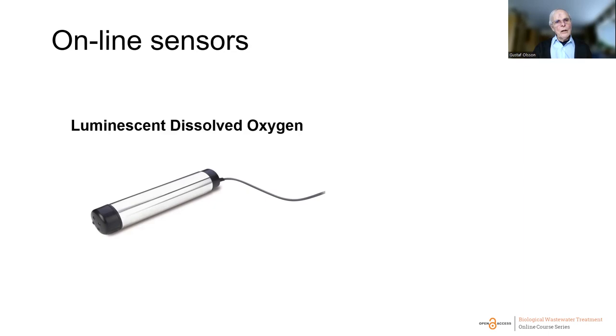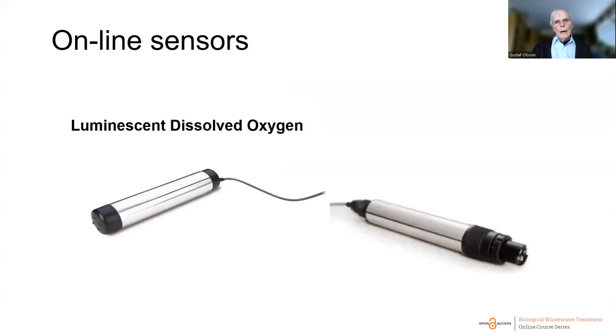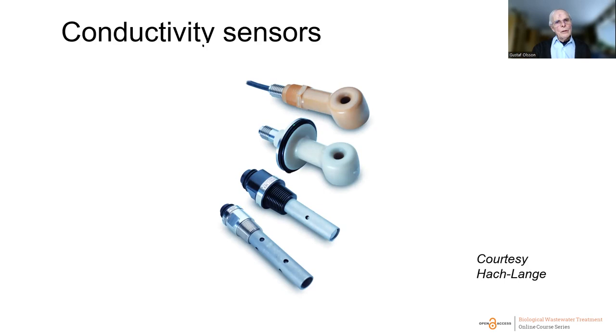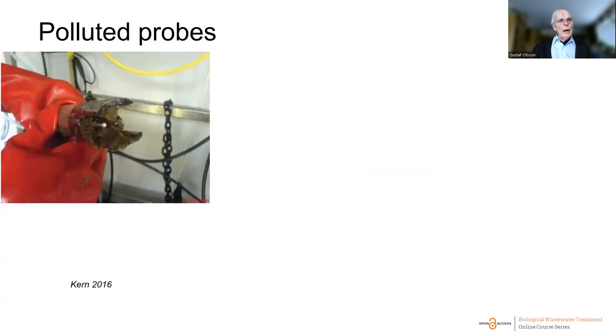As an example, here is a luminescence dissolved oxygen sensor. The sensors today — ammonia or DO sensors — are quite advanced, and cleaning and calibration are not required several times a day as they used to be in the early years. These sensors are now considered reliable by operators in general. There are also conductivity sensors that give other kinds of signals about the quality of the process behavior.